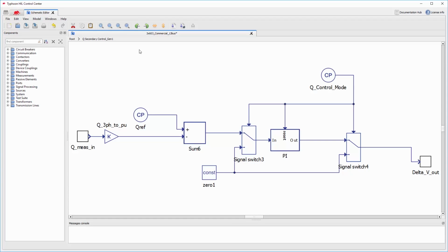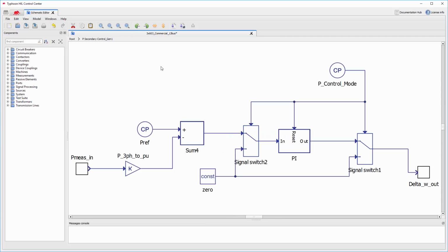Gen 1 has two secondary control loops, one to control the generator real power output, called P loop, and other to control the generator reactive power, called Q loop. The Q loop measures the reactive power at the terminal of the machine and compares it to a reference set. This reference passes through a PI controller that outputs small deviations in voltage reference to the exciter. It is possible to disconnect this loop from the rest of the machine control by setting the Q control mode input as 0. The P loop is similar to the Q loop, but this loop measures real power at the machine terminal and applies small deviations in reference speed to the governor. This loop can be disconnected by setting P control mode to 0.